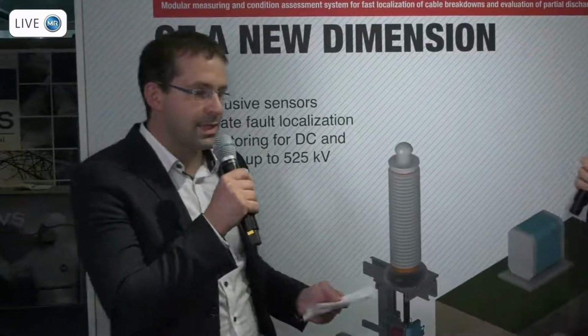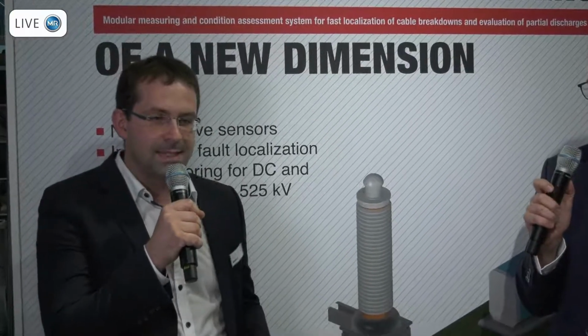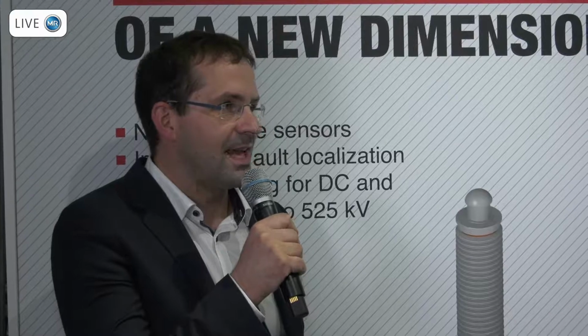Yeah, so at the end, what is the monitoring system doing in detail? In detail, or in general, today we have two functions of the system. The first function is fault localization. That means to find a fault if a cable breakdown occurs. And the second point is PD monitoring. That means to find small signals, but we will discuss these topics, to find small signals in the cables in order to understand the condition of a certain cable system.